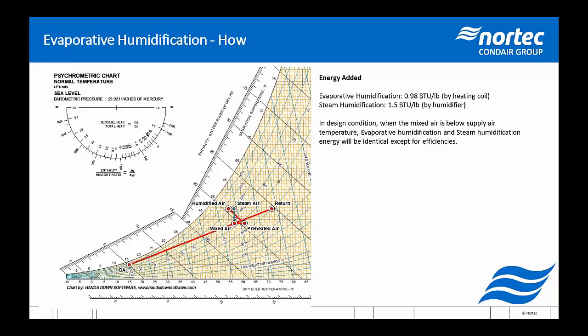So this is looking at basically a design condition day in this New York City building. It's cold. It's 15 degrees Fahrenheit, 16 degrees Fahrenheit. At that point, we can basically assume there's no moisture in the air. So no matter what, we will be humidifying this day. And our return air is somewhere in the 72, 73 degrees. And we want to be at about 40% because 40% is the optimal level for humidification. So if we were doing this with a steam system, we actually managed to meet mixed air temperature here at 55 degrees without doing any extra heat. And then, of course, we boil water and put the water in the air, and away we go. We're at our set point for our supply air temperature.